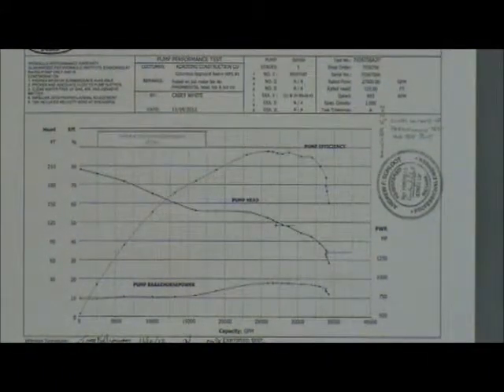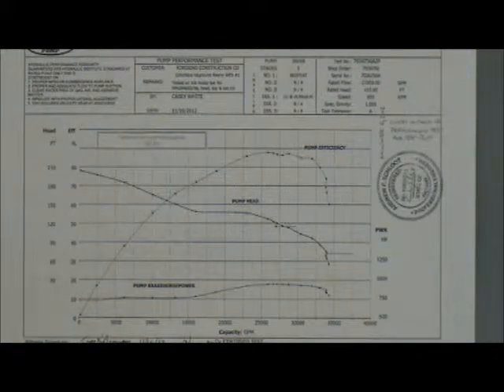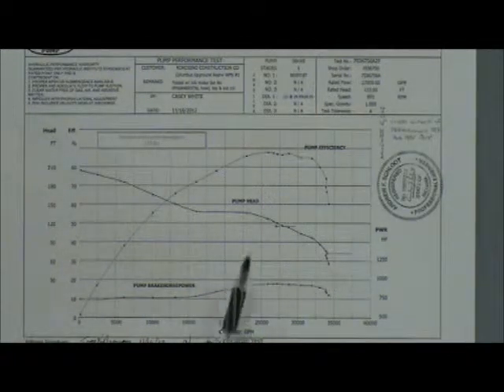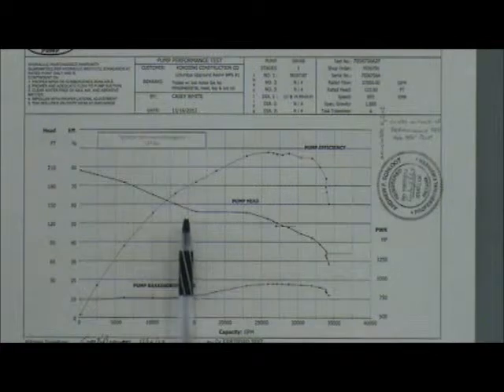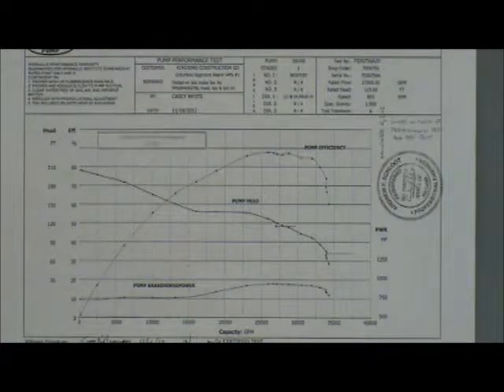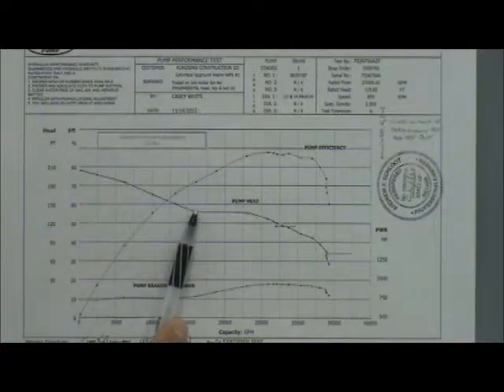This is the pump curve for this project. This is the design point right here at 27,000 gallons per minute. And then with our control scheme, you can also go into low flow mode, which goes back to about half of that rate, at about 14,000 gallons per minute. About right there on the curve.